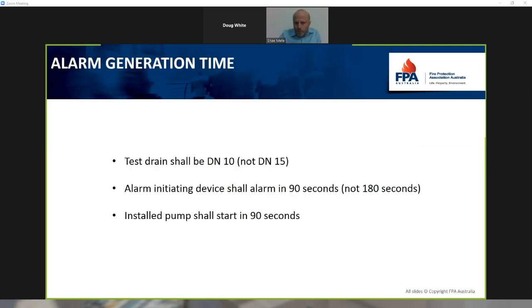Test drains can be reduced from 15mm drains to 10mm. This is because these are residential applications. That's the worst case scenario from a testing point of view. We want to make sure that any alarm initiating devices operate in 90 seconds, not 180 seconds, and that they operate from an orifice similar to a residential sprinkler, which is smaller than for a commercial sprinkler typically. So it's a smaller K factor, and that's where we use the DN10, the 10mm test drain, not the big kahuna, the 15mm, which is going to flow the equivalent of 2, maybe even more sprinklers. So that's not really a fair test.